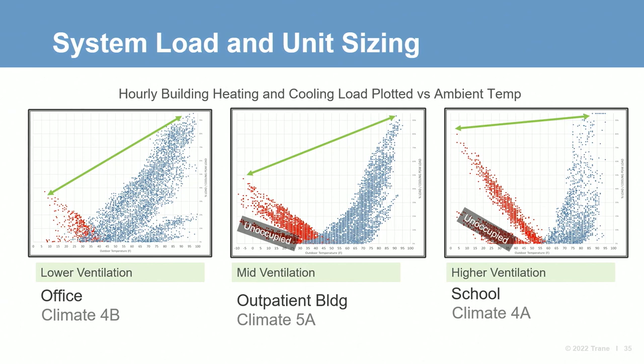Another observation from the charts is that the commercial buildings with primarily comfort heating and cooling have a limited simultaneous heating and cooling demand during prime economizing times. This reduces the energy benefit of waterside heat recovery. However, there are other benefits to properly sized heat recovery that we're going to discuss later.